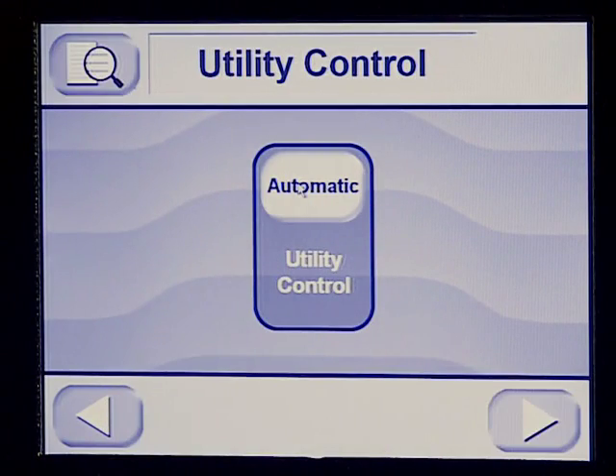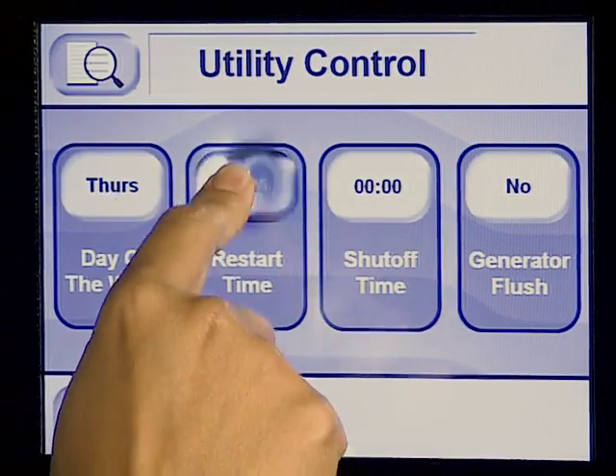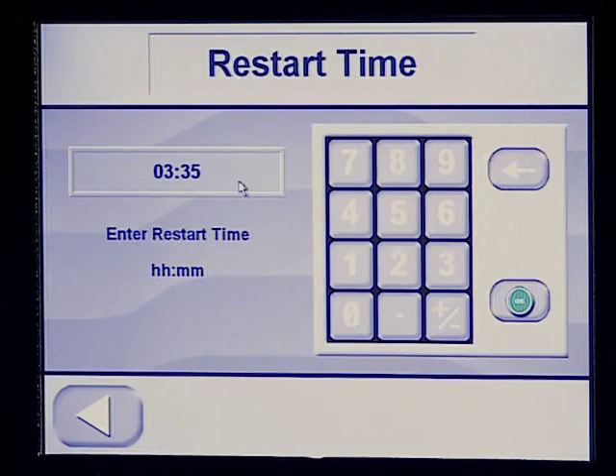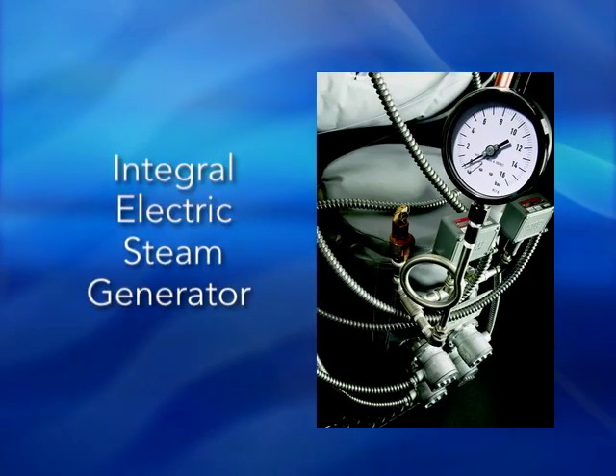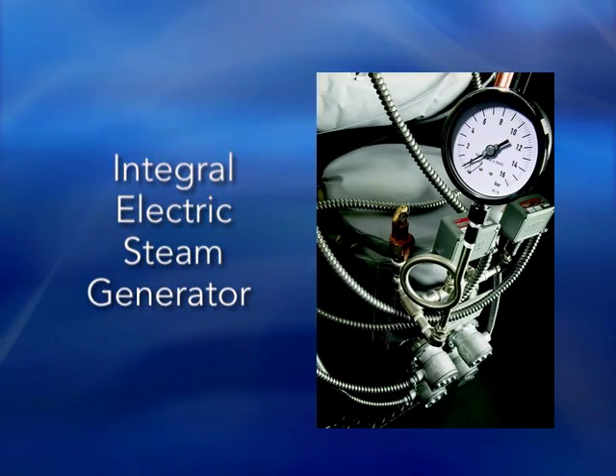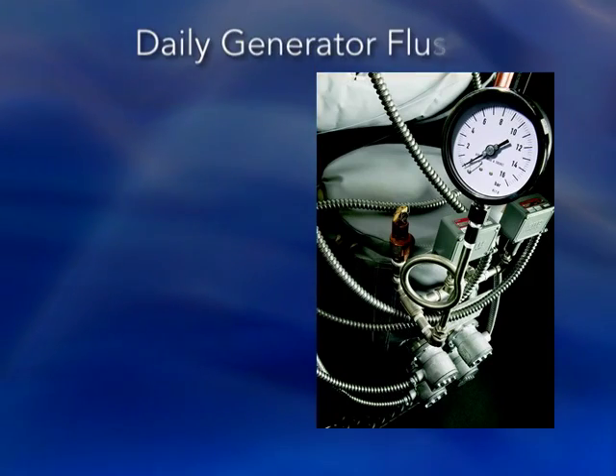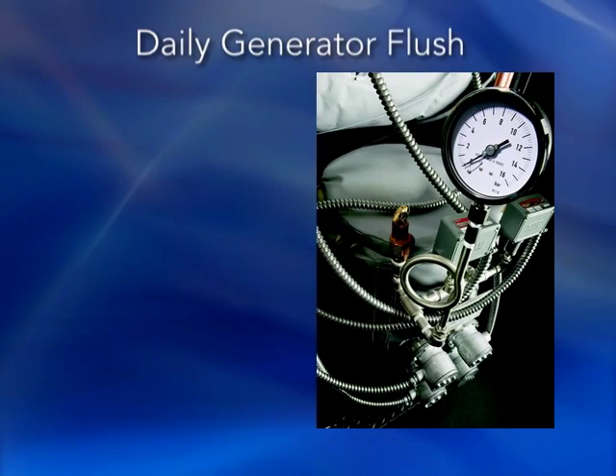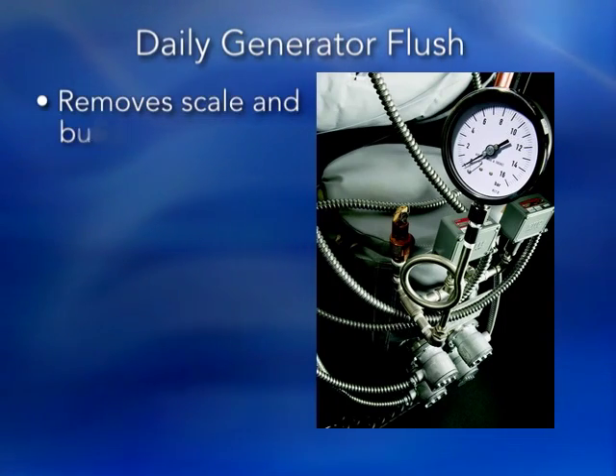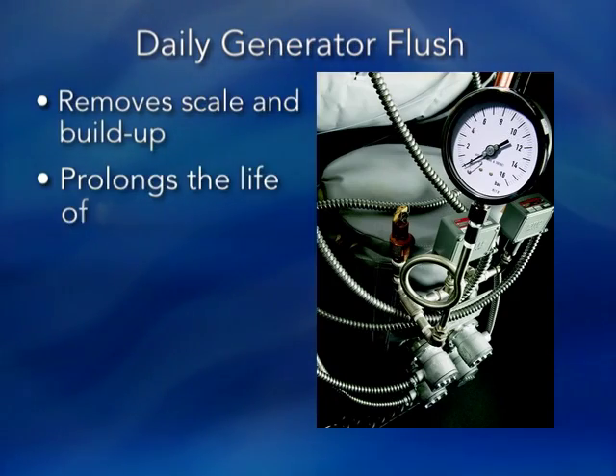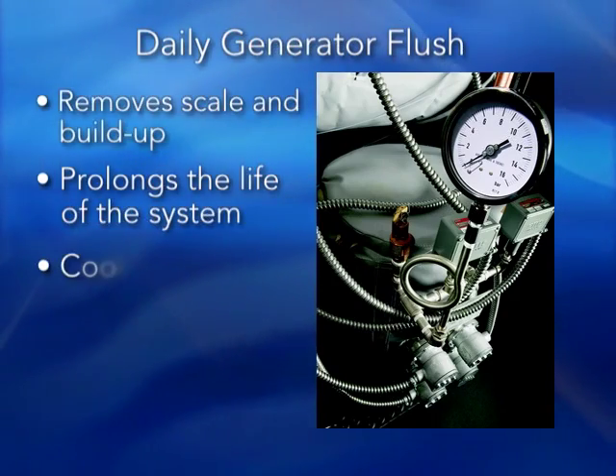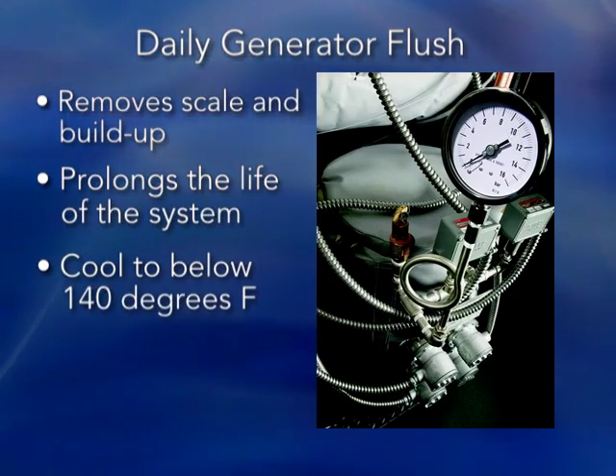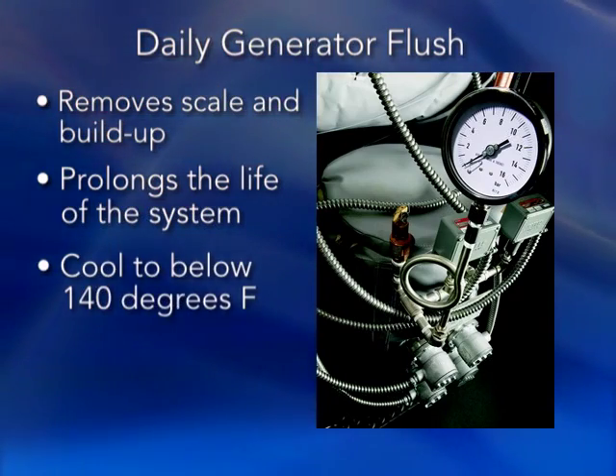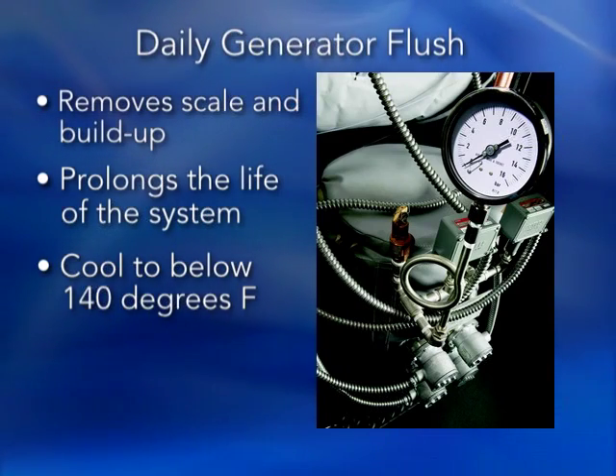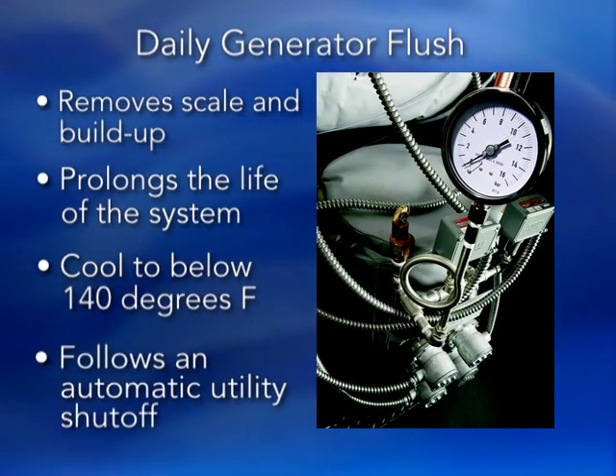Select Manual or Automatic. If Automatic is selected, you can program the restart and shutdown times for each day of the week. If your sterilizer is equipped with an integral electric steam generator, the sterilizer can be set to perform a daily generator flush. Performing a generator flush daily removes scale and buildup from the generator and prolongs the life of the system. The generator must cool to below 140 degrees Fahrenheit before an automated flush can occur. Therefore, the automated generator flush only occurs following an automatic utility shutoff.